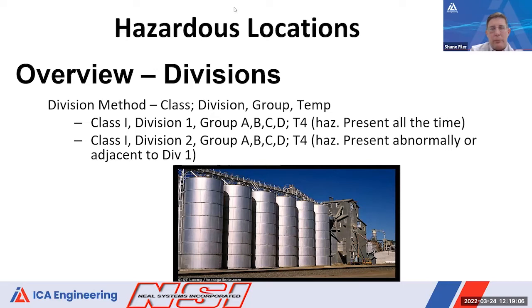My particular plant, the bulk tank storage area, we have an adjacent drum-off area. So we just have a roofed area. It's not enclosed due to the fire regulations in New York. And that's class 1, division 1 is that area. We have like a 50-foot boundary there where things are treated differently because we're actually dissipating fumes, flammable fumes. All my storage areas are within closed garage doors. They're adjacent to that, and that's division 2.